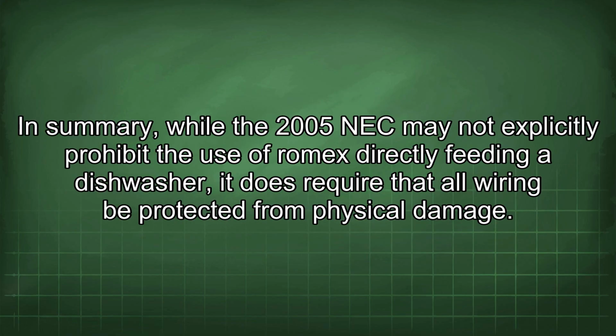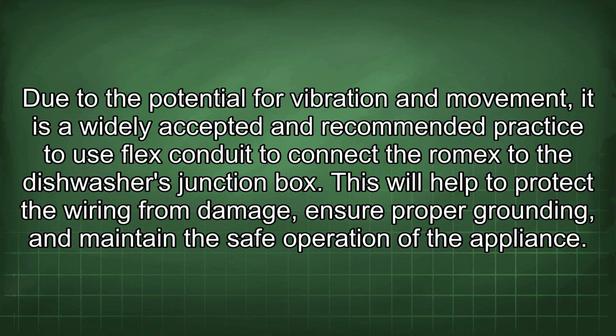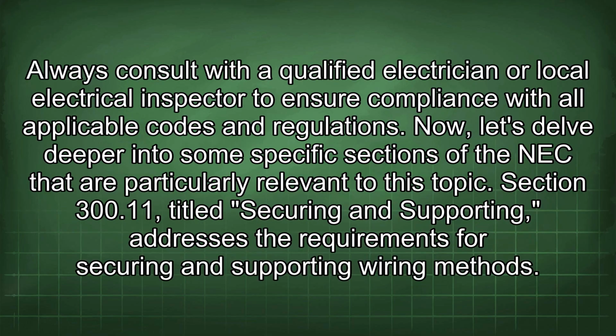In summary, while the 2005 NEC may not explicitly prohibit the use of Romex directly feeding a dishwasher, it does require that all wiring be protected from physical damage. Due to the potential for vibration and movement, it is a widely accepted and recommended practice to use flex conduit to connect the Romex to the dishwasher's junction box. This will help to protect the wiring from damage, ensure proper grounding, and maintain the safe operation of the appliance. Always consult with a qualified electrician or local electrical inspector to ensure compliance with all applicable codes and regulations.